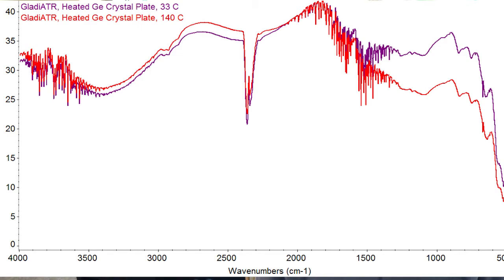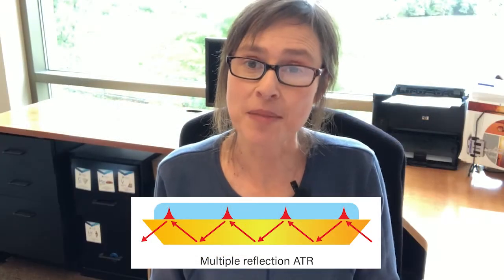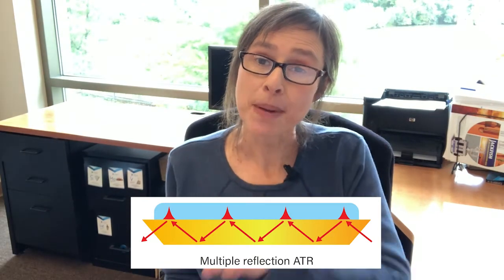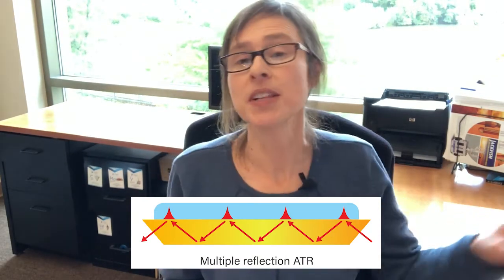We have minimal drop-off in energy throughput. Now let's contrast that with the HATR, which is a multiple reflection ATR with a long crystal — 80 millimeters. With that beam bouncing down that 80 millimeter long crystal, it's quite a long beam path. Let's see what happens when we heat it up.